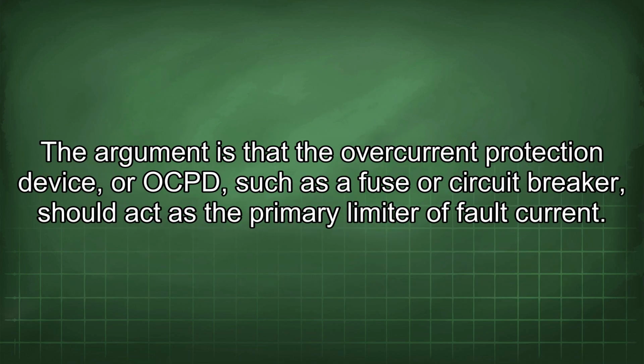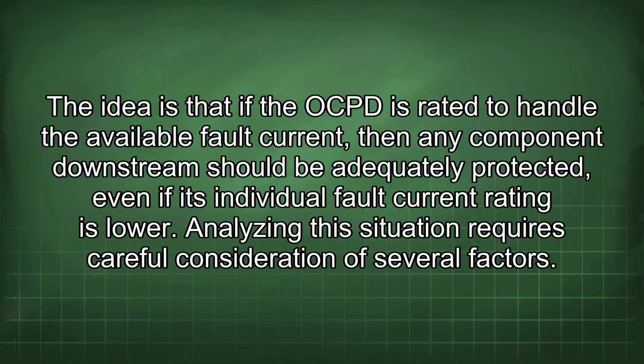The argument is that the overcurrent protection device, or OCPD, such as a fuse or circuit breaker, should act as the primary limiter of fault current. The idea is that if the OCPD is rated to handle the available fault current, then any component downstream should be adequately protected, even if its individual fault current rating is lower.